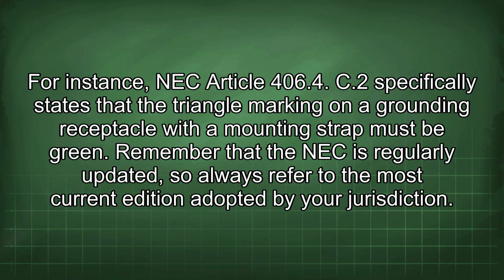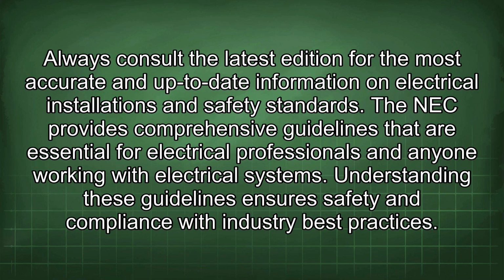For instance, NEC Article 406.4 C2 specifically states that the triangle marking on a grounding receptacle with a mounting strap must be green. Remember that the NEC is regularly updated, so always refer to the most current edition adopted by your jurisdiction. Always consult the latest edition for the most accurate and up-to-date information on electrical installations and safety standards.